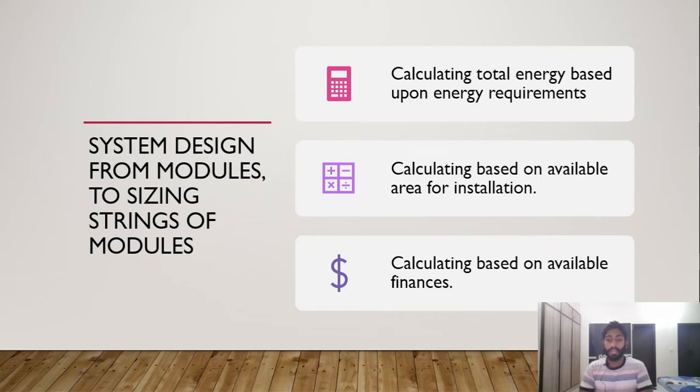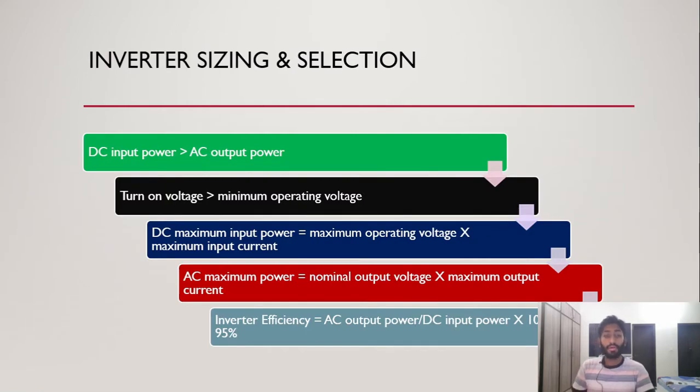Now it goes to inverter sizing and selection. If you have an inverter in front of you and you look at the specifications sheet or at the back, you have to look at the DC input power - that is always going to be greater than the AC output power because of efficiency. Normal inverter efficiency is around 90 to 95 percent, so the DC input has to be higher than the AC output. You also have to look at the turn-on voltage, which is the minimum voltage that needs to be higher than the minimum operating voltage in order to operate.